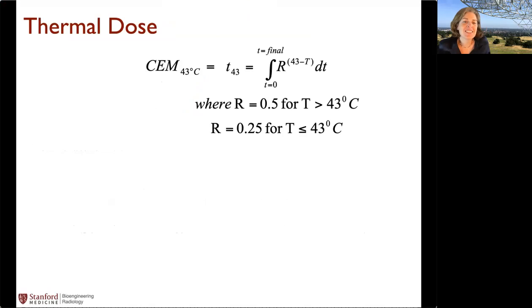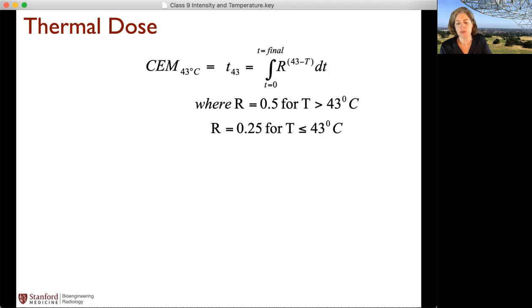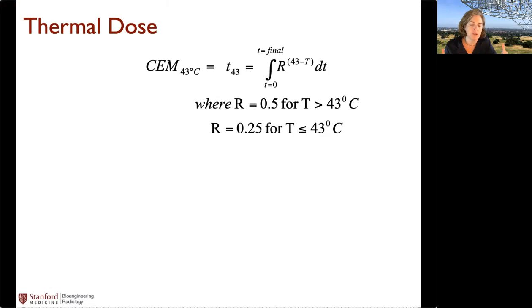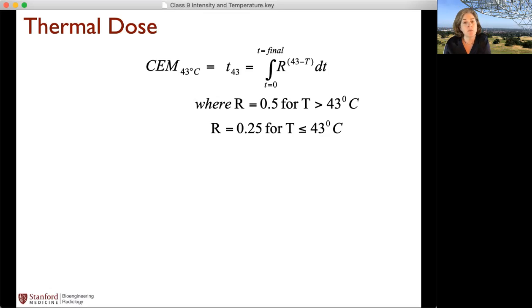All right, so people have looked for a long time at this concept of thermal dose, which takes into account both the temperature and the amount of time it's at that temperature. They've looked at a number of different situations, both cells in a dish as well as in vivo, and come up with this parameter, which is the cumulative equivalent minutes as if it was at 43 degrees. It's a way to take these different time-temperature curves and relate them to each other. So if you can relate all of them to the number of minutes that would have the same amount of damage at 43 degrees, that is kind of what we're trying to do here. And so there's a relationship here.